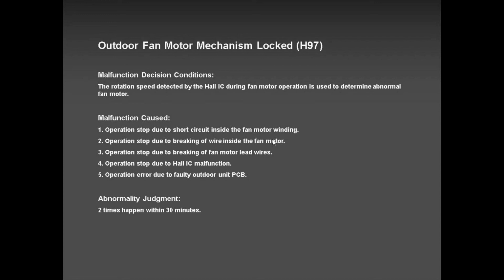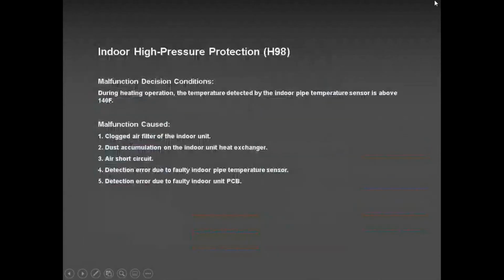I will talk about error codes that are very common. This one here, H97, outdoor fan. I can tell you 99% of this error code was caused by snow. Snow got accumulated inside the unit. Probably the unit was not running. The homeowner was not around, on vacation, came back, and the snow got frozen and the blades were not moving. That's one possibility. Another possibility is the unit is not defrosting. So what happens? The unit keeps freezing up and freezing up, and the ice keeps building inside and stopping the fan blade. That's where the problem happens.